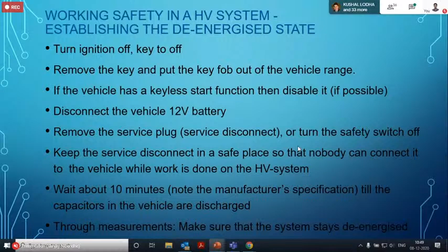Once the de-energized state is established and there are no faults in the systems, there shall be no torquing procedure by the person operating on the high voltage systems, no electrical energy available anywhere, and no voltage on the capacitors or HV cables is ensured. So the HV battery is isolated from the rest of the HV systems.